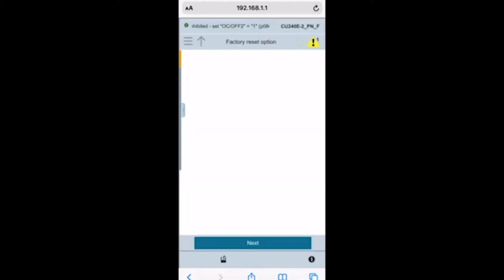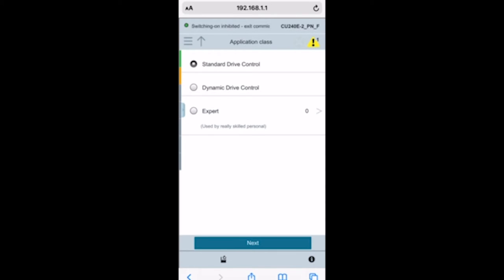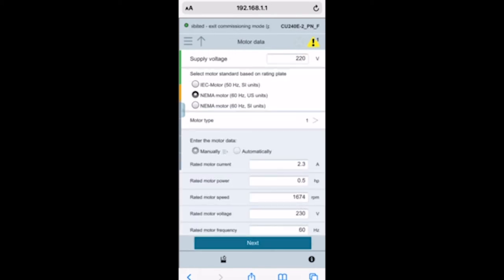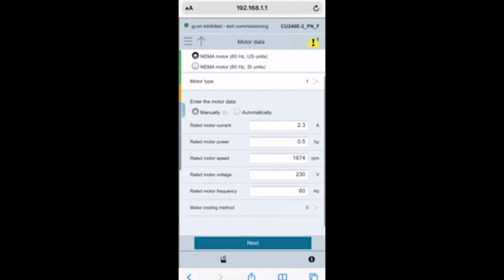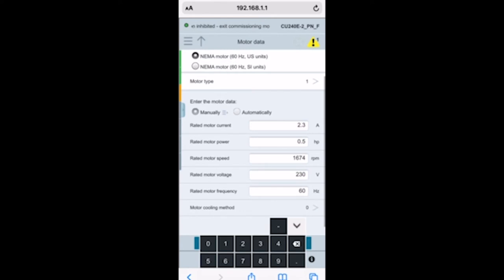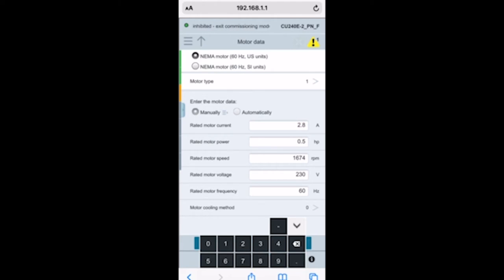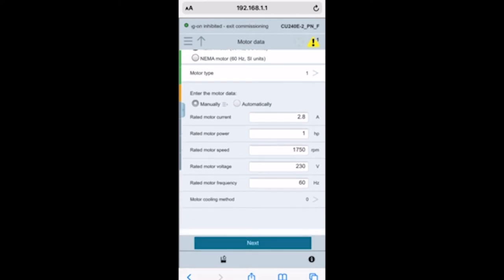Once it's done, you'll see I got my successful check mark, so we'll hit okay. Now we're going to start entering information to commission our drive. I'm doing standard drive control, working with 230 volts NEMA motor. The amperage on my nameplate is 2.8 amps and I've got a one horsepower motor, 1750 RPM.